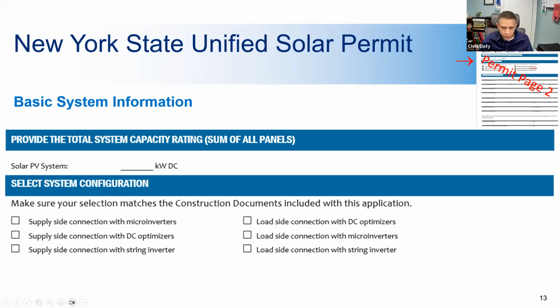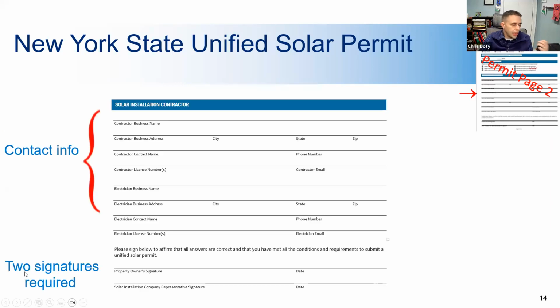And as I mentioned, if you know these 3 things, the size, the type of inverter, and the type of connection you have, you can generally know what to look for in the rest of the documentation. So the next section down is detailed contact information for the contractor and the electrician. It includes contractor and electrical licensing numbers where they're needed. It's important to notice that 2 signatures are needed at the bottom of this application: the property owner and the contractor. Both of them are attesting to the accuracy of the information on the application. So you want to definitely make sure both signatures are there.